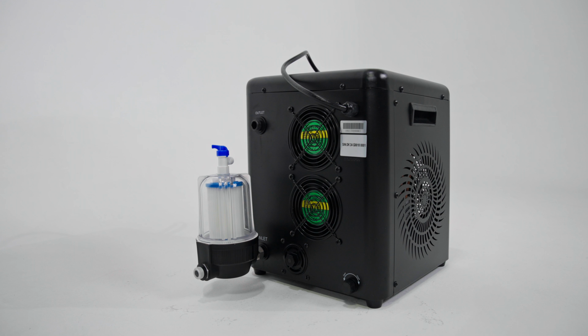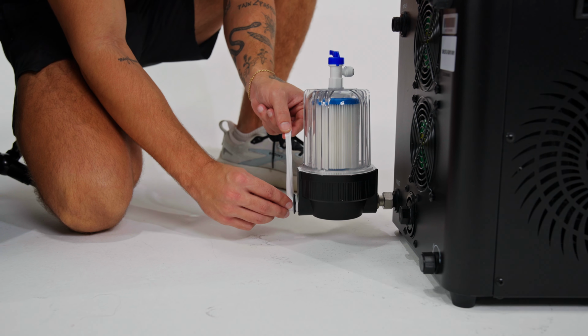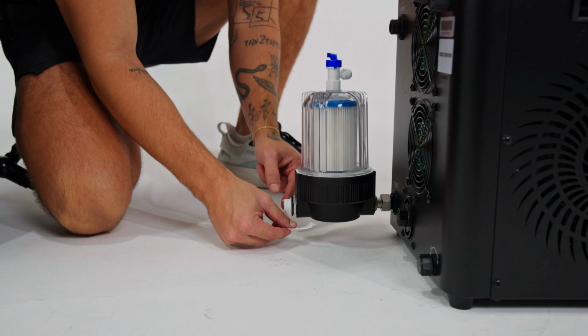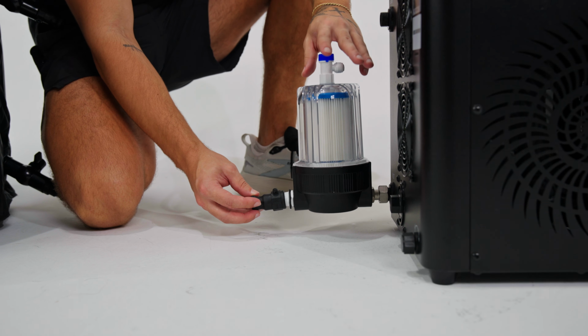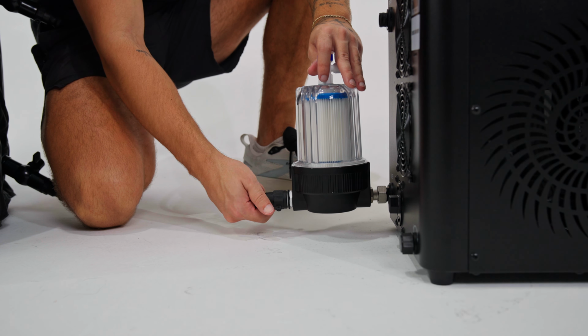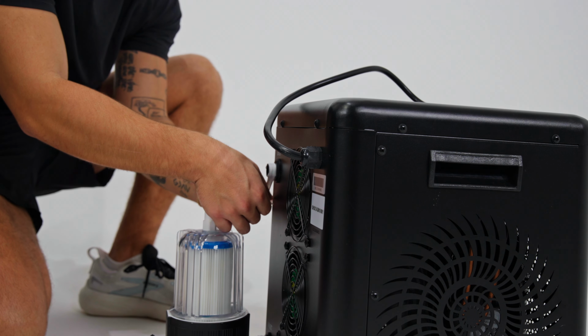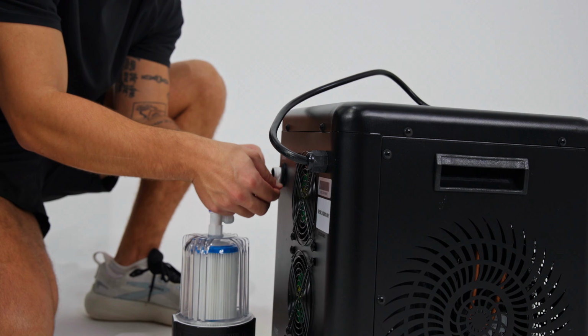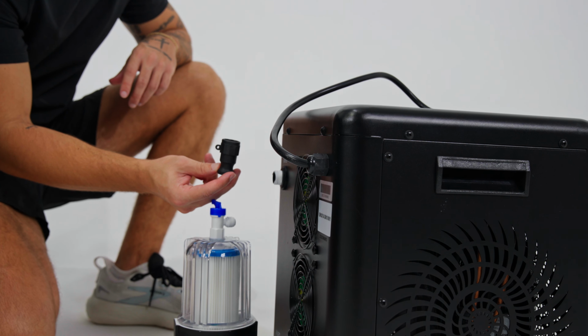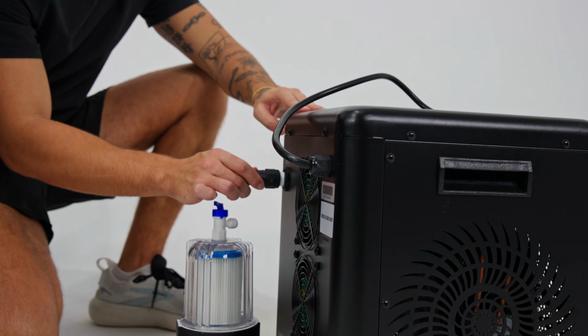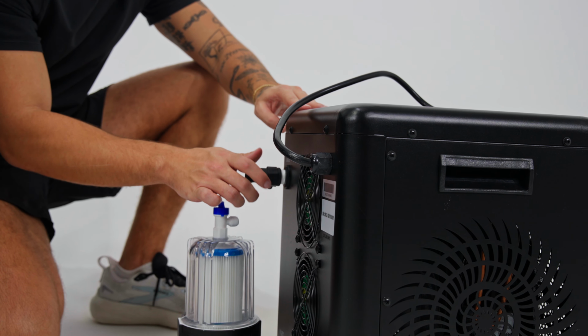There are now just 2 open threads, one on the filter canister and one on the outlet port of the chiller. Start by wrapping a few rounds of Teflon tape around the canister's outlet thread. Then screw one of the female fittings onto the filter canister. Repeat the same process for the outlet port. Wrap it with Teflon tape just like before. Now attach the second female fitting onto the chiller outlet. Your fittings are installed. Now let's connect the hoses.